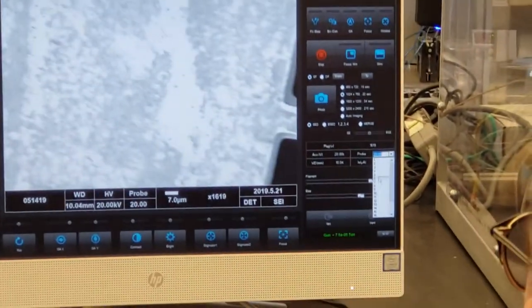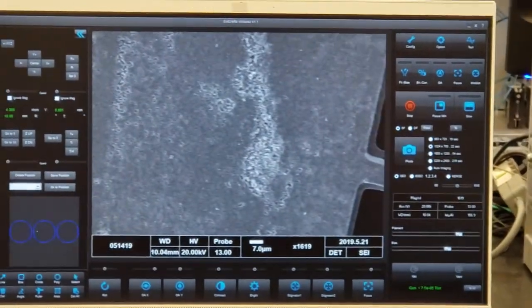If you open up the spot size all the way up to 20, we're going to pull roughly 16,000 counts a second, which is a ton. It's great for us. So let's even lower that right now to, let's say, spot size 13. Bring up the contrast, this way we still have good imaging quality, and we can still have our 1,500 counts a second, which is great up here, right? So, percentage of dead time, counts per second. So far, so good on these two things.